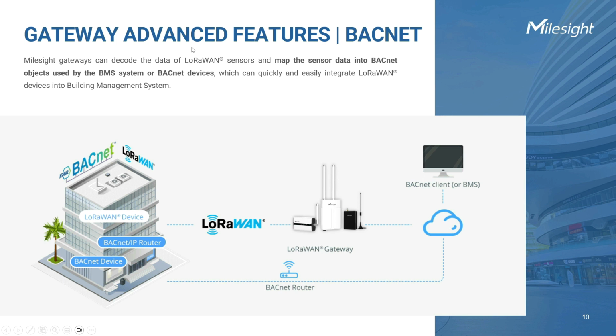Building automation systems based on traditional hardwired BACnet protocols can be costly, difficult to extend, and inflexible when it comes to adding new functions. However, LoRaWAN technology provides a better way to manage functional spaces by enabling an extension of BACnet capabilities. While LoRaWAN is not a replacement for BACnet, it can enhance the automation and control of various building systems, such as lighting, heating, ventilation, air conditioning, and security.